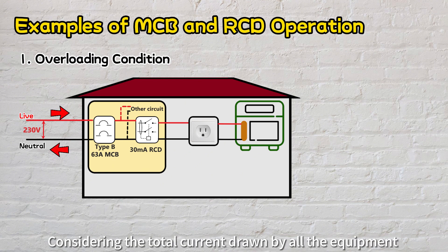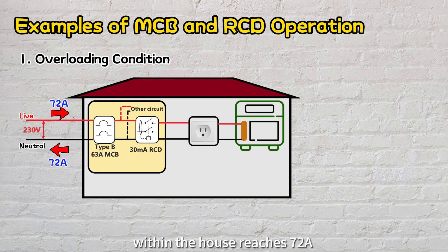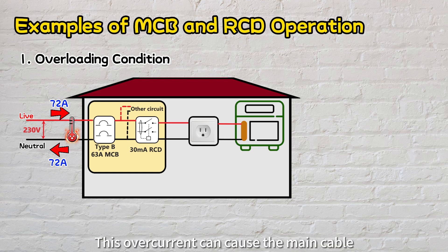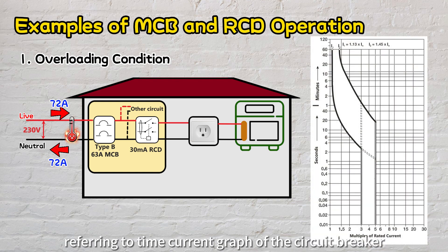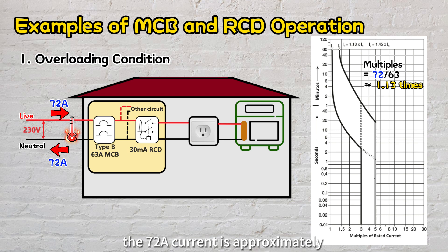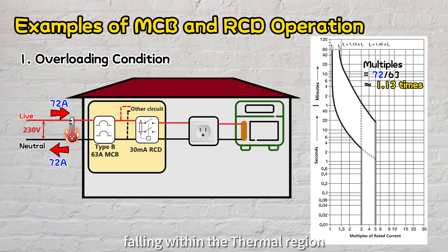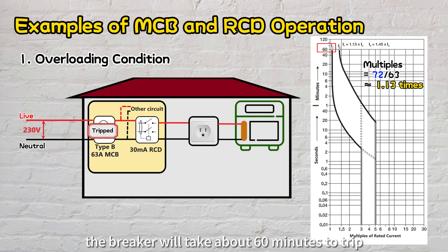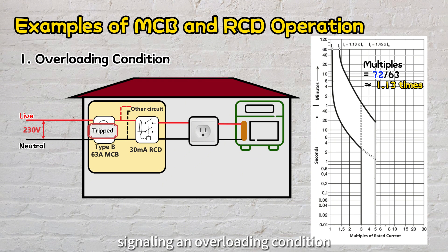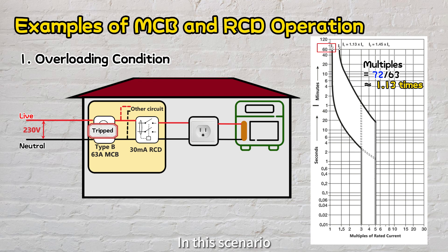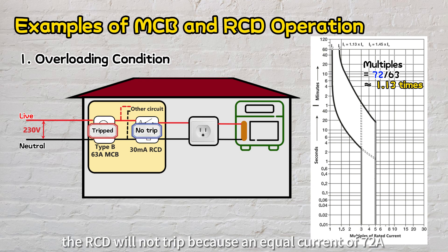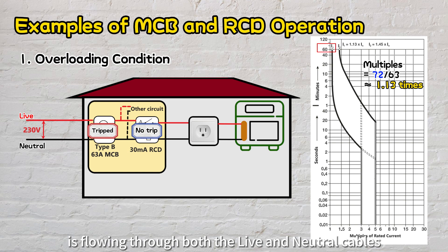Considering the total current drawn by all equipment within the house reaches 72 amps, slightly surpassing the 63 amps MCB rating. This overcurrent can cause the main cable and bimetallic plate within the circuit breaker to heat up. Referring to the time-current graph, the 72 amps current is approximately 1.13 times the rated current, falling within the thermal region. Consequently, the breaker will take about 60 minutes to trip, signaling an overloading condition and preventing a potential fire hazard. In this scenario, the RCD will not trip because an equal current of 72 amps is flowing through both the live and neutral cables.